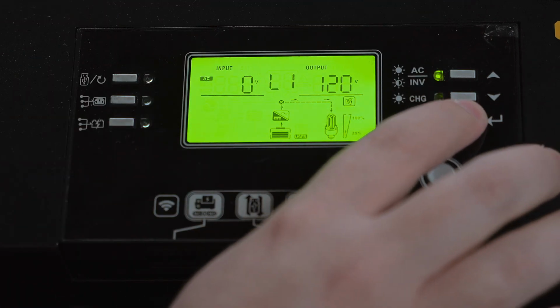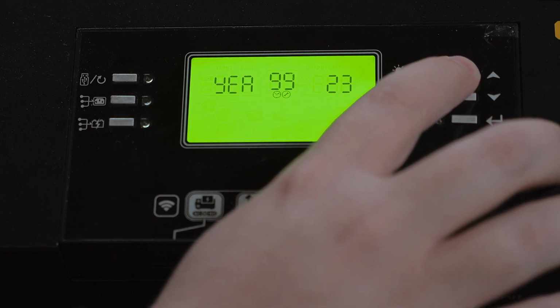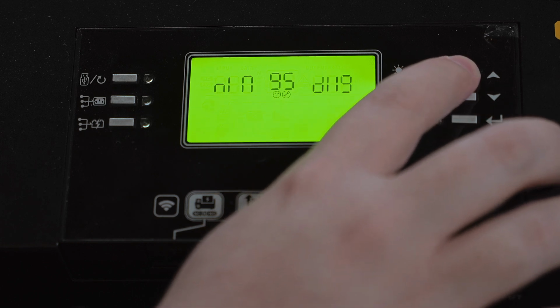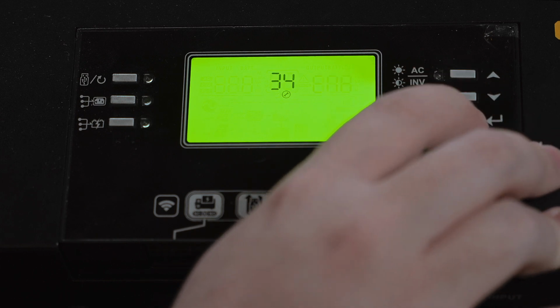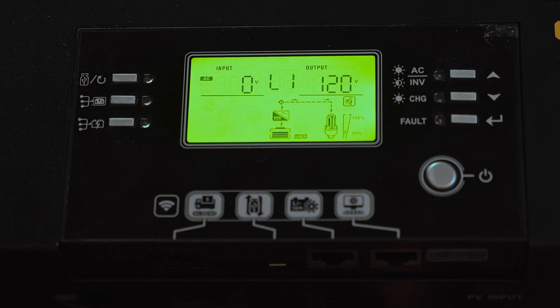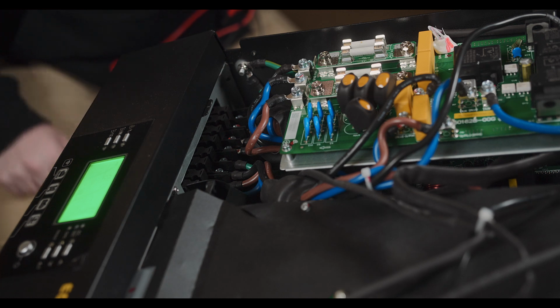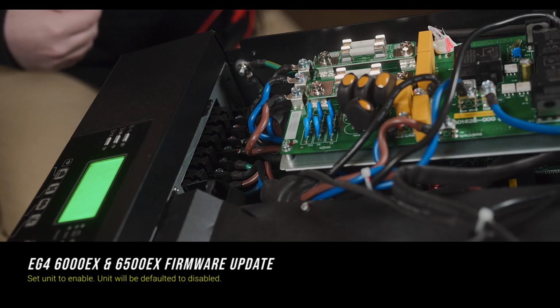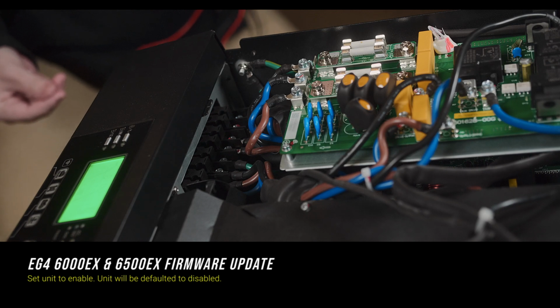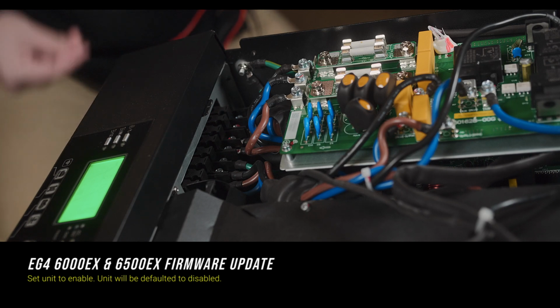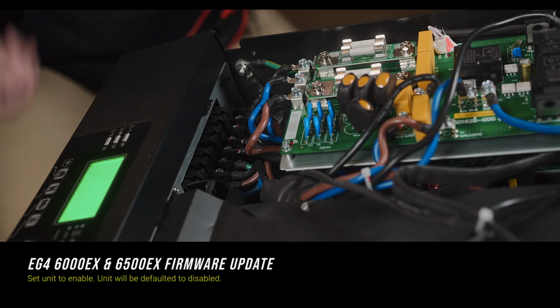Let's go ahead and change the setting. On the 6000EX, it is setting 34, and on the 6500, I believe it is 42. Let's set that to enable and back out. This setting does require a power cycle, so you'll need to turn the unit off, let it fully shut down, and turn it back on to get the setting to save. While this is shutting down, a key note to remember is that if you use this new firmware on your unit in a stationary setting, you do need to go in and set this to enabled, because it defaults to disabled, which effectively has that ground neutral bond.